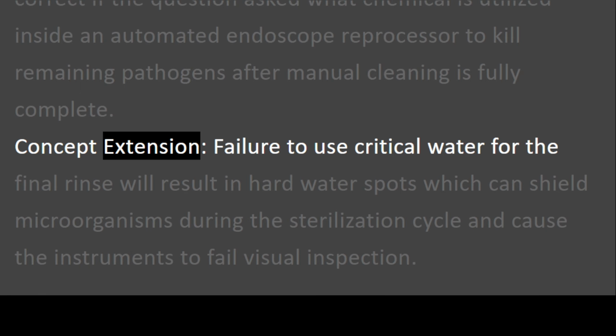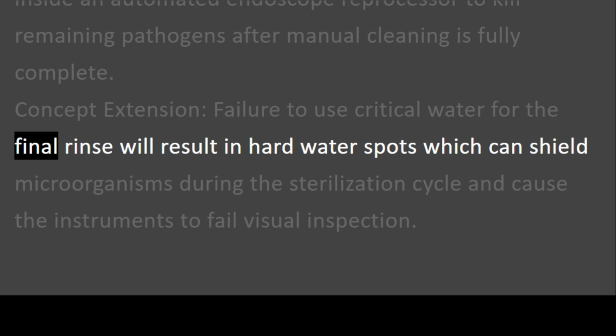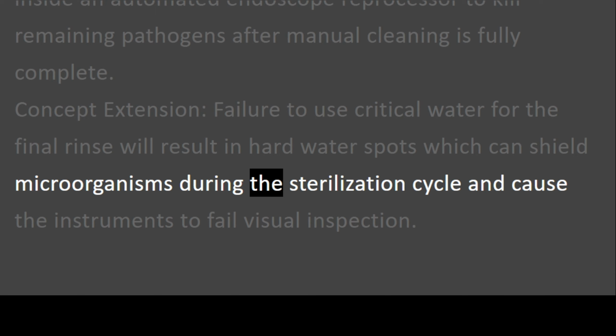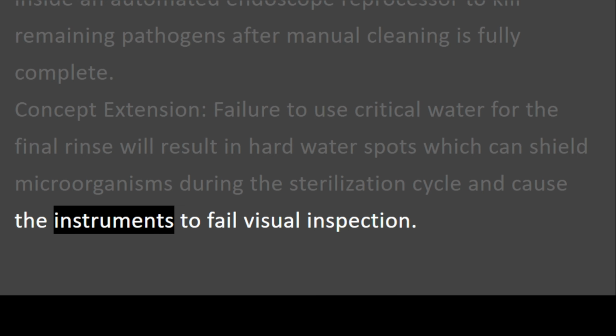Concept extension. Failure to use critical water for the final rinse will result in hard water spots, which can shield microorganisms during the sterilization cycle and cause the instruments to fail visual inspection.